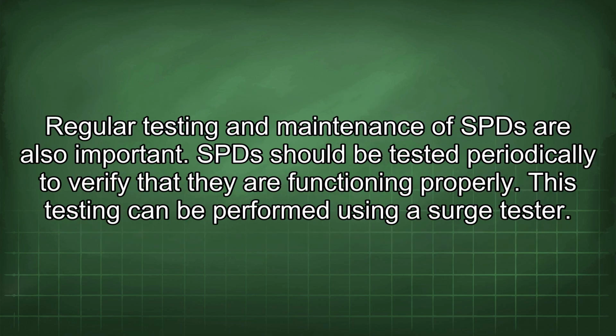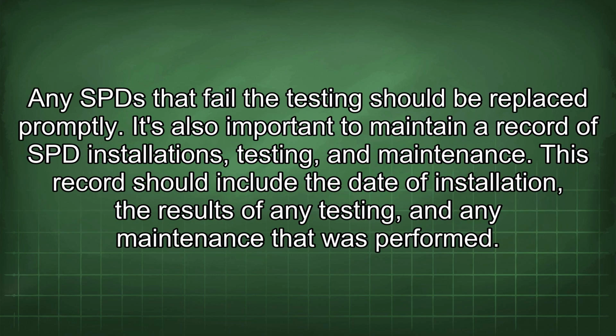Regular testing and maintenance of SPDs are also important. SPDs should be tested periodically to verify that they are functioning properly. This testing can be performed using a surge tester. Any SPDs that fail the testing should be replaced promptly. It's also important to maintain a record of SPD installations, testing, and maintenance. This record should include the date of installation, the results of any testing, and any maintenance that was performed.